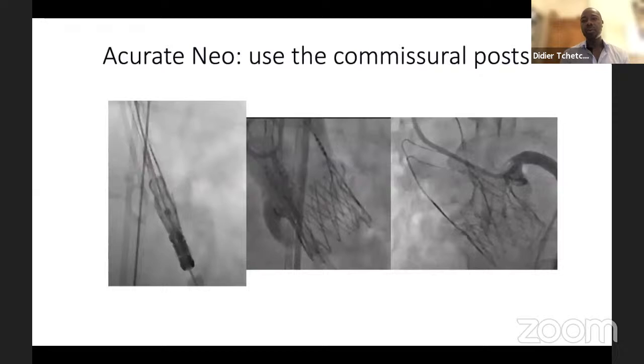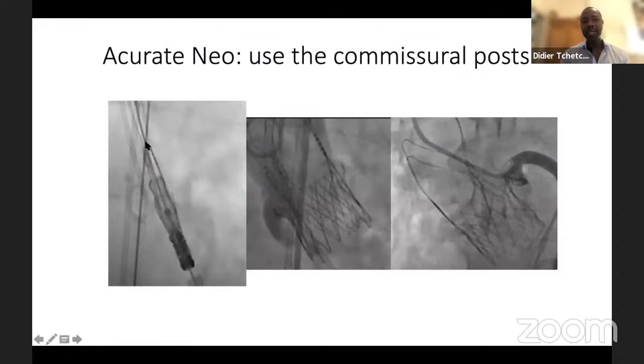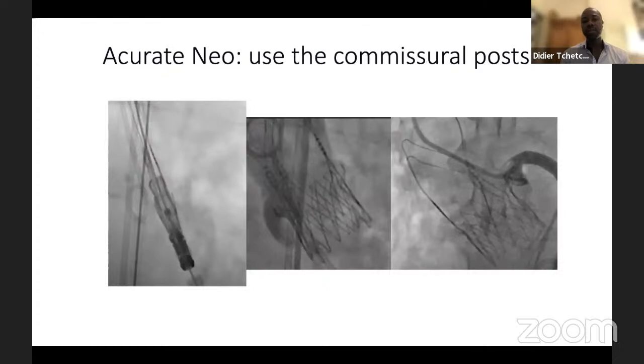Importantly, when targeting three o'clock, one post should appear extremely flat — like a thin line — and this should be the post facing the commissure between the coronary sinuses. For the Accurate Neo, keeping the flush port at 12 o'clock achieves adequate commissure alignment in the vast majority of patients. Before starting deployment, confirm in the cusp overlap view — most often an RAO-cranial projection — that one post appears as a thin flat line, with three dots facing the commissure between the right and left coronary cusp.